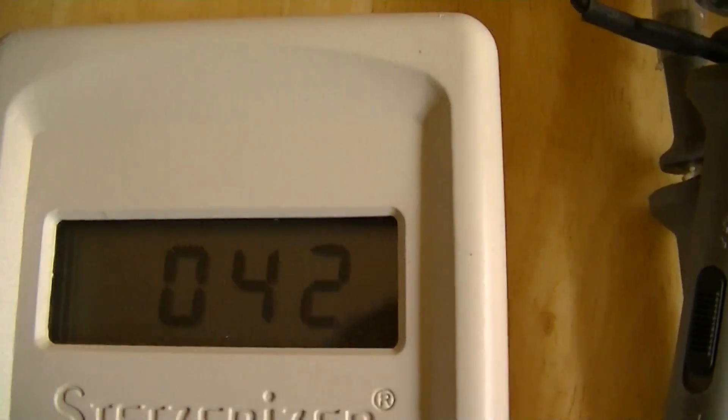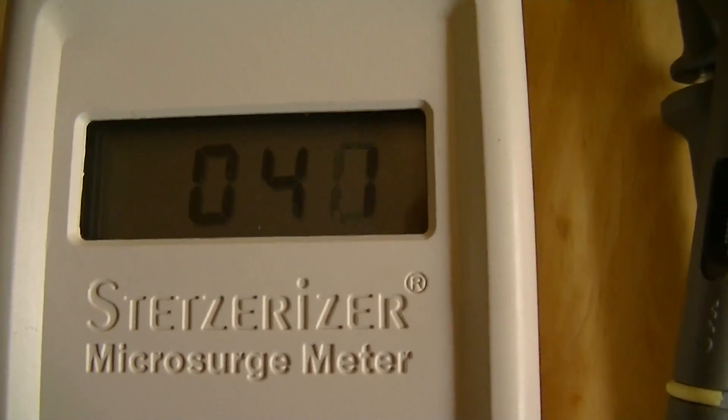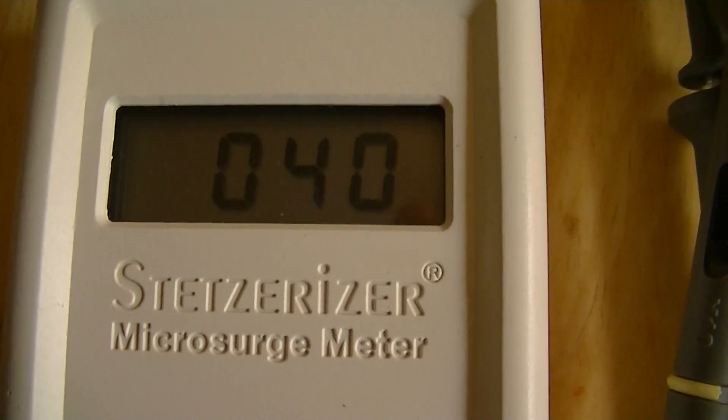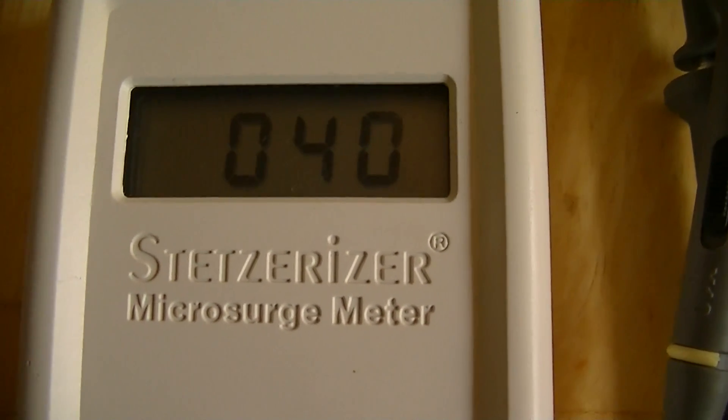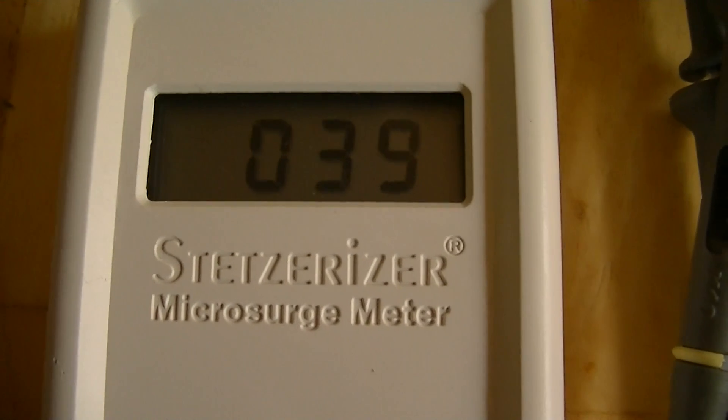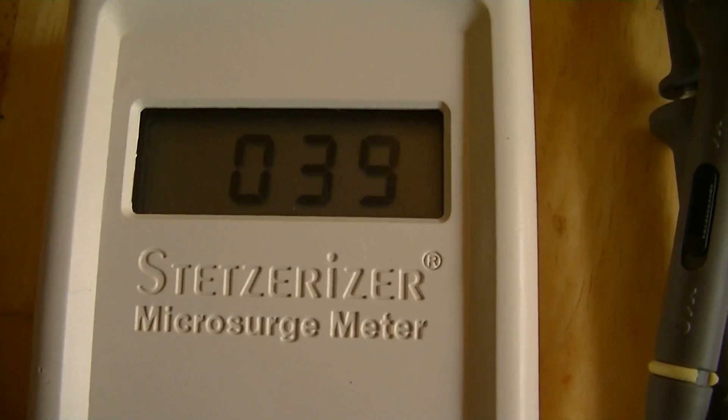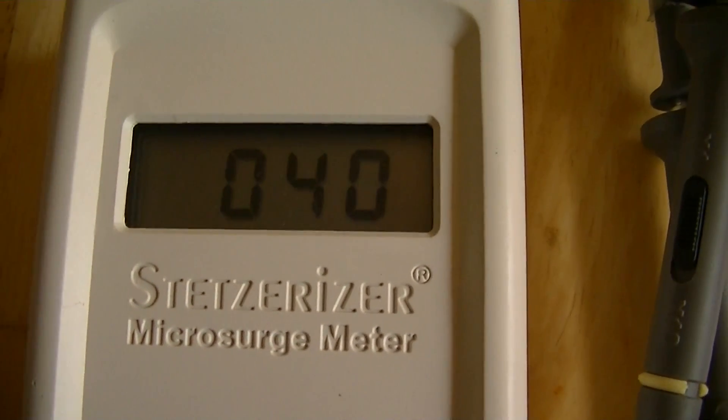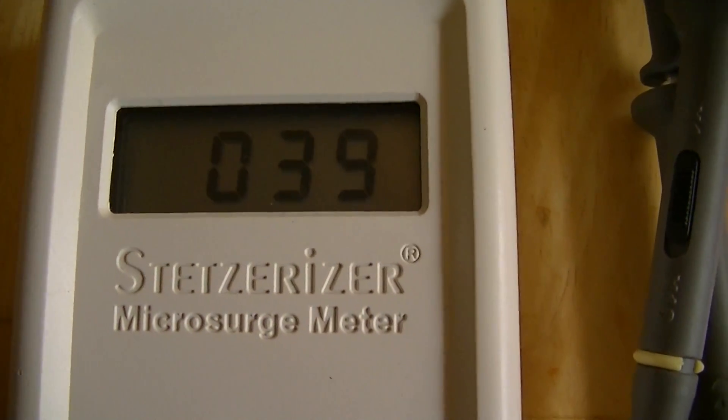Our lights have just switched off, so I'm going to switch them back on again. Our lights are back on, capacitor is plugged in, and you can see the effect that plugging in the capacitor has had on this meter. We're actually now below what the manufacturer states is what you want. The manufacturer says anything above 50 is a problem, so we're now down at 40, which the manufacturer would say is acceptable.